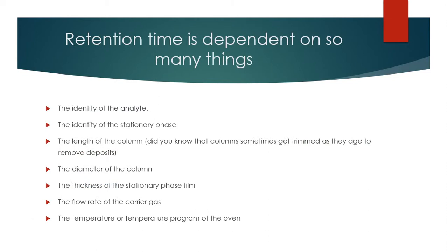Retention time is dependent on many things: the identity of the analyte, the identity of the stationary phase, the length of the column (columns are sometimes trimmed as they age to remove deposits), the diameter of the column, the thickness of the stationary phase film, the flow rate of the carrier gas, and the temperature or temperature program of the oven.